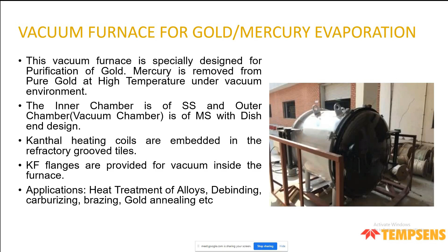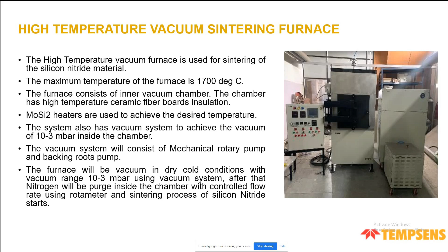We just now supplied this to, I think, DRDO for sintering of silicon nitride material. Temperature goes up to 1700 degrees centigrade, using molybdenum disilicide heating elements, with two vacuum pumps—mechanical and a backing roots pump—used for sintering silicon nitride.